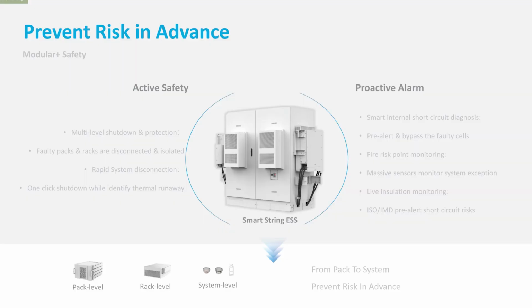Prevent risk in advance. On our ESS, we have active safety, with multi-level shutdown and protection. Faulty packs and racks are disconnected and isolated. So if we detect a pre-warning that a battery pack has some lithium plating or short circuit current, we disconnect that pack automatically. Then you do a warranty claim and we give you a new pack.